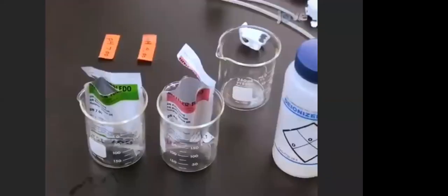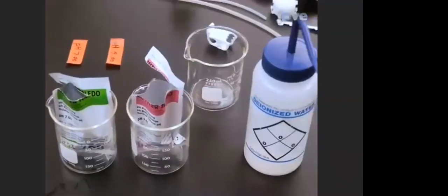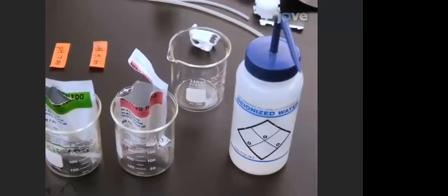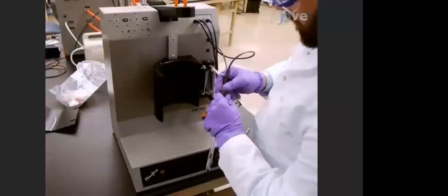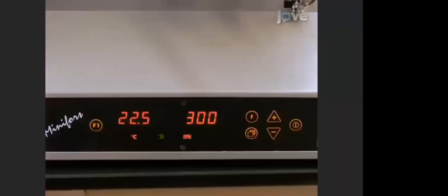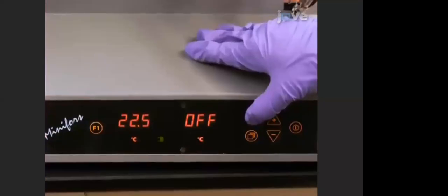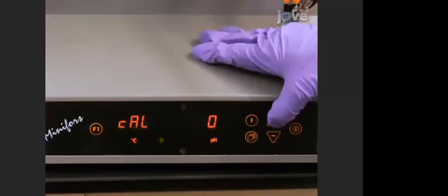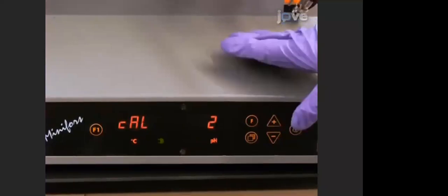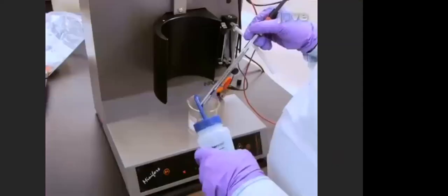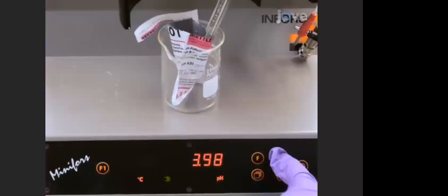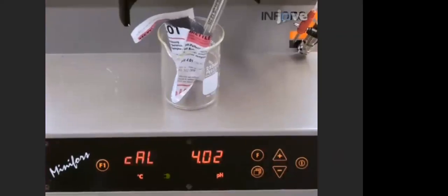To calibrate the pH probe, gather 2 reference buffers in small beakers, a wash bottle, and a wash beaker. Hook the pH probe up to the fermenter and turn it on. Scroll to the pH parameter, and then, using the menu button, scroll to the Cal option and press Enter. Select 2 for 2-point calibration. Wash the pH probe tip and submerge it in the low reference buffer. The value on the fermenter will stabilize. Using the plus and minus keys, adjust the displayed value to match the value of the pH reference buffer. Once it stops blinking, press Enter.